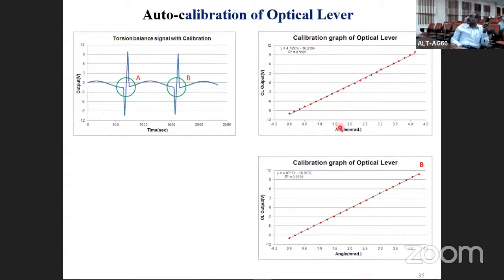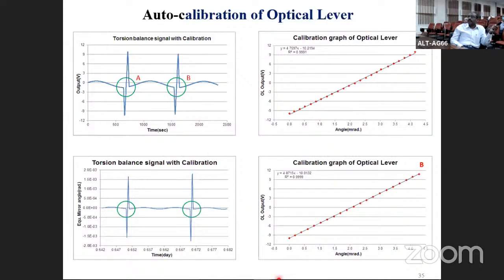Now there is one more error which happens, and which I will show now here. Well, you have successfully done it at the turnaround time, you have programmed it well, but when you are parking your CP, that's the compensating plate, when you are driving the electromagnetic, it may happen because of the mechanical backlash of the forward and reverse direction of the motion and things like that, you may not end up at the right place. So for example, in this case, it doesn't park exactly at the same position. In this, it has happened. So it can give some kind of offset. And imagine a case where you keep on calibrating your system on a day-to-day basis, you may end up providing drift into the system, and such drift should be taken care of.